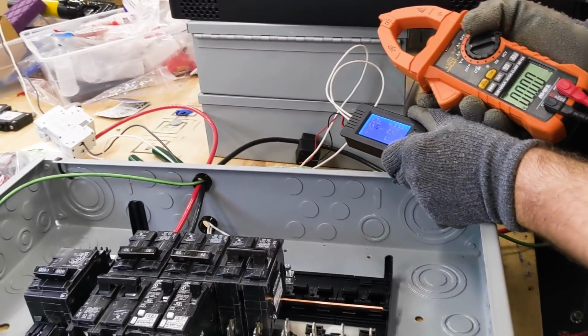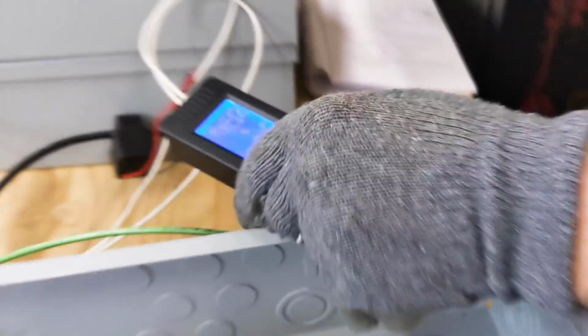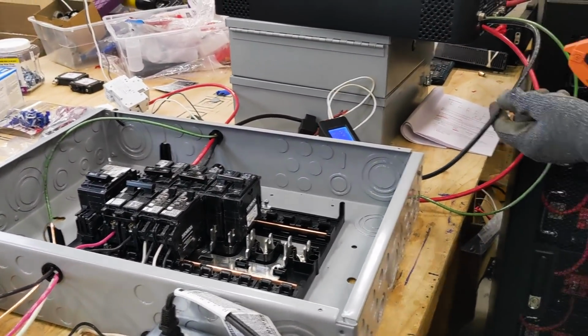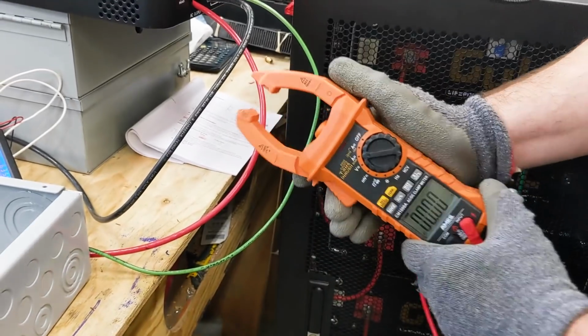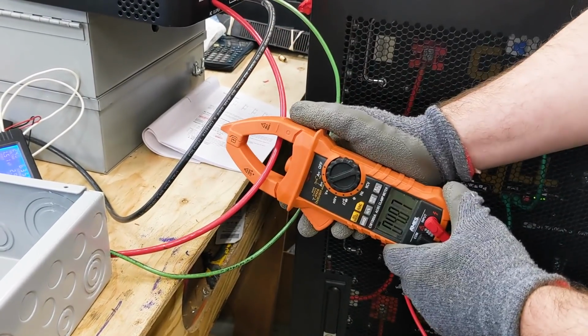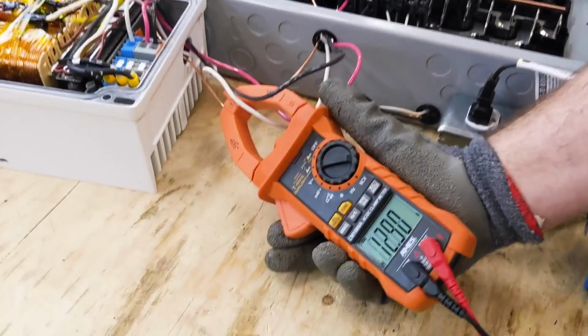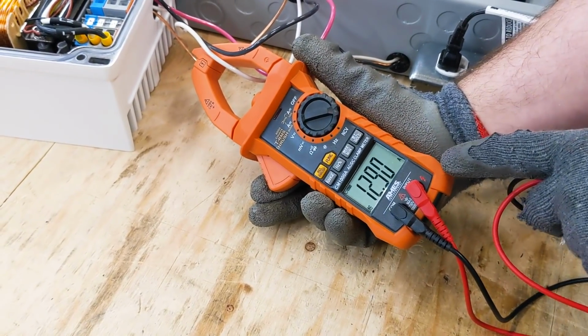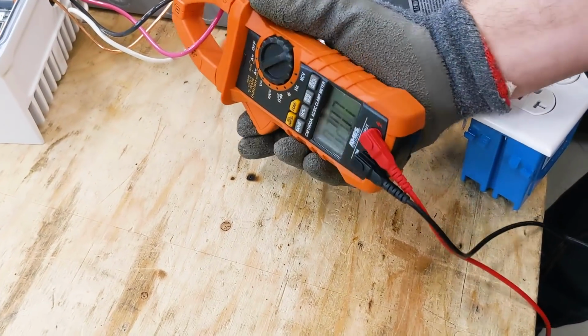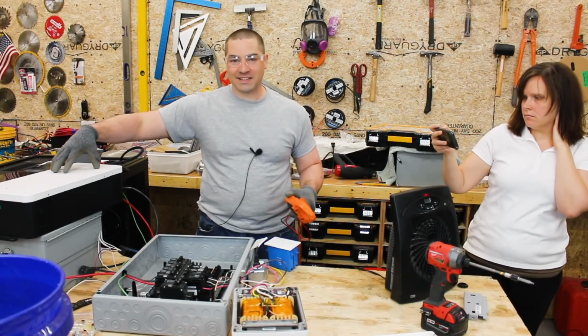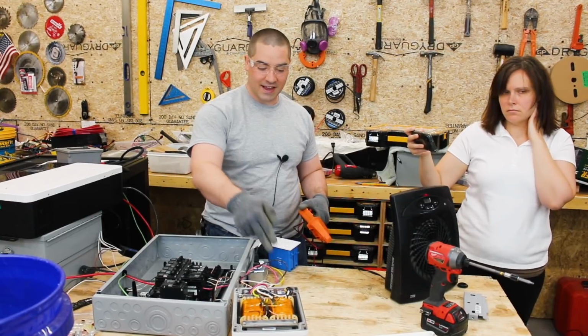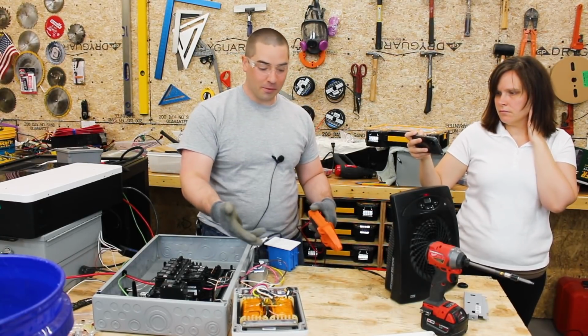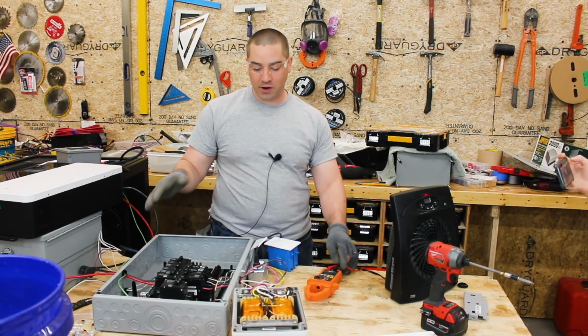We're pulling 6.3 amps. So that's going to be 6.3 amps on both of the hot legs. So the point is that we have two equal, 6.4 and about 6.4. So we're drawing equal amps on each of these hot legs. But now we'll jump over to the neutral, which is coming off the auto transformer, and we have 12.9 amps off the auto transformer. Off one of the hot legs, 6.3, and off the other one, 6.3. This is supplying an even amount on both of the hot legs, and then the neutral is actually supplying double that because we are only having a load on one of the neutral legs.